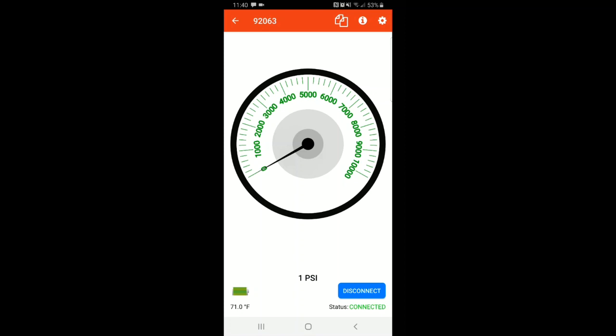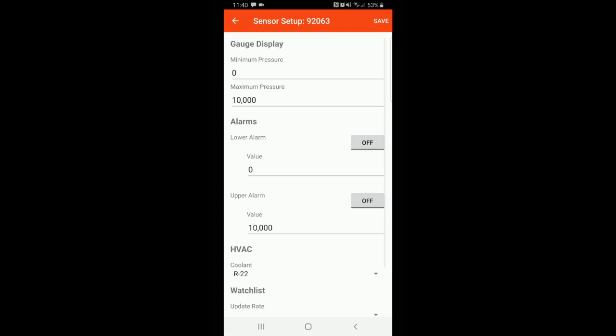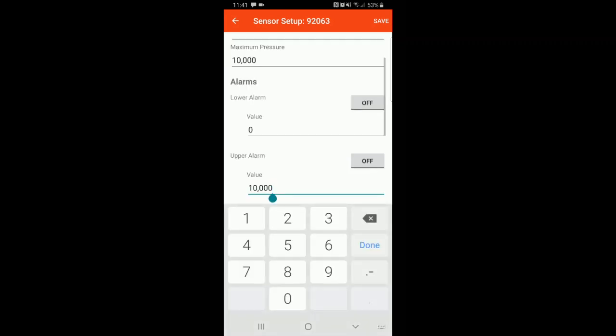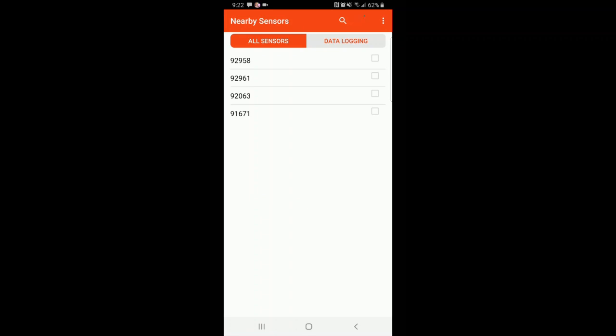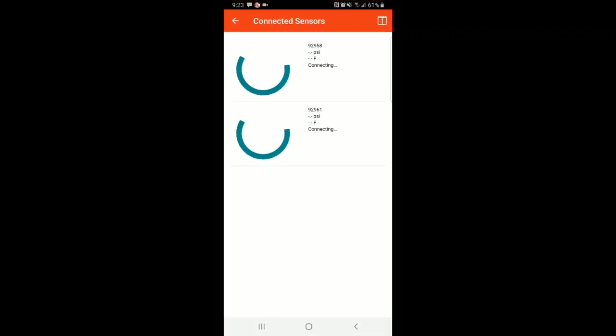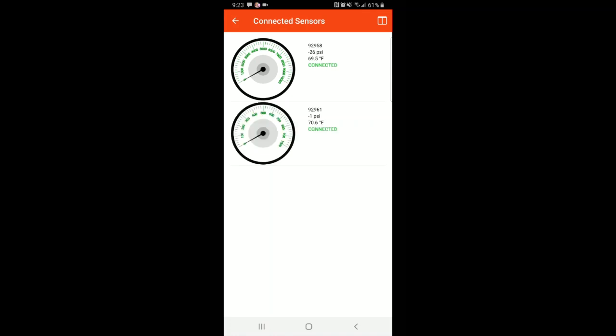If alarms have previously been enabled, you can access this under the settings for each individual sensor, and that is the gear selection in the top right-hand corner of this screen. When this populates, you have the ability to adjust the minimum and maximum pressure shown on the gauge display, as well as to turn on and off individually both the upper and lower alarms, and you also have the ability, of course, to change these values as shown here. An additional feature of the application is the split screen mode, which allows you to view the values from multiple transducers at once. When you select more than one, you simply go up to the top right-hand corner and click on the connect button. And the values will be displayed as shown here.